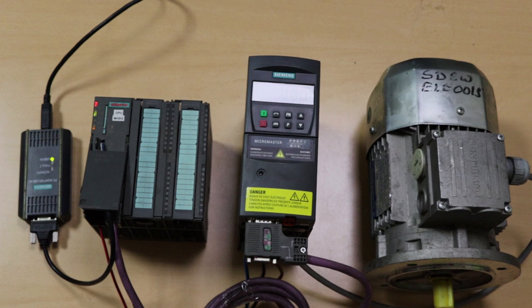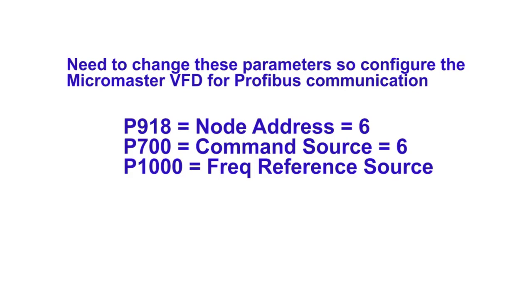First we have to make some settings in the VFD and change some parameters so that our VFD is compatible to communicate with the S7300 PLC via Profibus. The first parameter is P918, which is the node address. We have to enter the node address of the VFD — in our case I have entered address 5. The second parameter is P700, the command run source, and we have to set it to 6. By setting it to 6 we configure the VFD to take the run command from the S7300 PLC via Profibus.